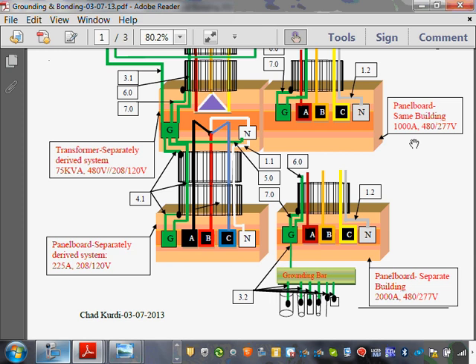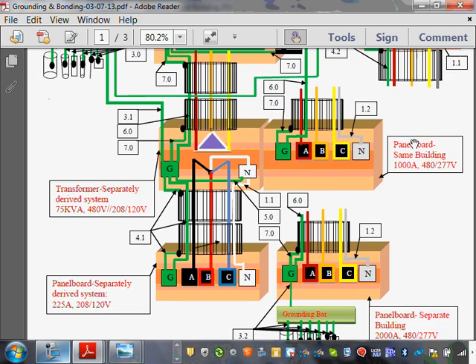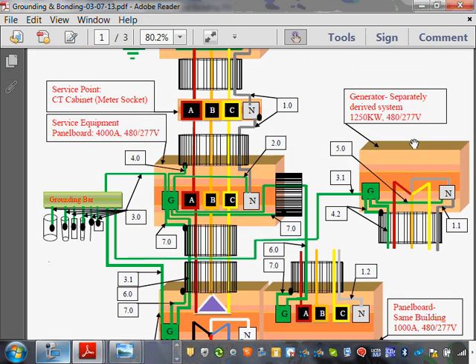Any questions? Comments? Let me take you to the last one, guys, on grounding and bonding, which is the generator that I know you guys were waiting to hear about for a long time, right? So now I have separately derived system transformer. That's a load, right? A transformer is a load, even though it's a source of power. Ultimately, the transformer does not generate power. It receives its power from the system, converted to a different amperage and voltage level. That's what transformers are, to match the equipment.